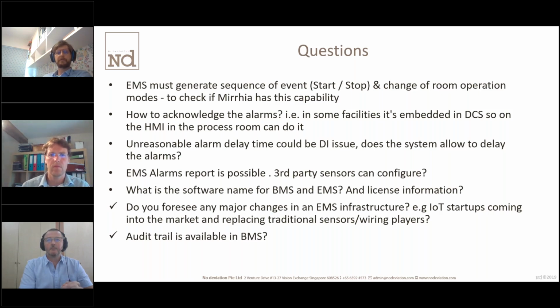So Mirrhia has the possibility to have different alarm thresholds, which you can base on the activity in the room, correct, Nicolas? Yeah, exactly. So we have those thresholds I've shown you during the demo. And also if you want to set the system in decontamination mode, where you don't want to have any alarm at all, it's possible. We will keep the continuous monitoring. So we will keep monitoring the information all the time, but you can decide if you have alarm or not, and what kind of threshold you want to apply.